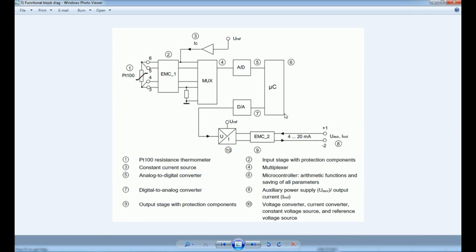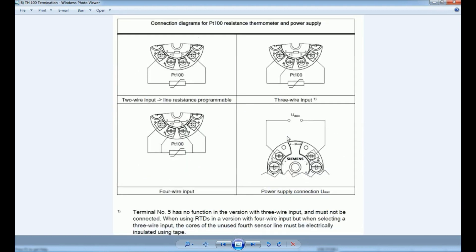This is the block diagram of the controller. The PT100 temperature sensor, RTD or thermocouple, is connected to the controller. From there, by multiplexing we get a signal in analog form, which is converted analog-to-digital and given to the microcontroller. The microcontroller then converts it into a digital signal, and we get a 4 to 20 mA loop via a voltage-to-current converter, and those signals are used as the HART signal.